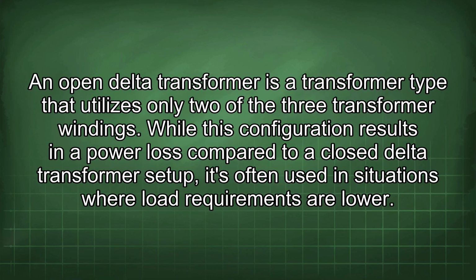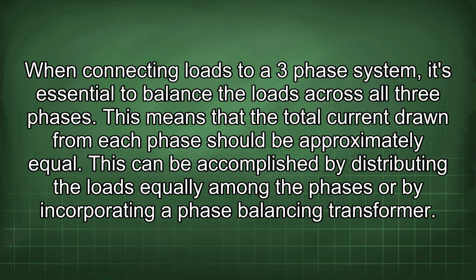An open delta transformer is a transformer type that utilizes only two of the three transformer windings. While this configuration results in a power loss compared to a closed delta transformer setup, it's often used in situations where load requirements are lower. When connecting loads to a three-phase system, it's essential to balance the loads across all three phases. This means that the total current drawn from each phase should be approximately equal. This can be accomplished by distributing the loads equally among the phases or by incorporating a phase balancing transformer.